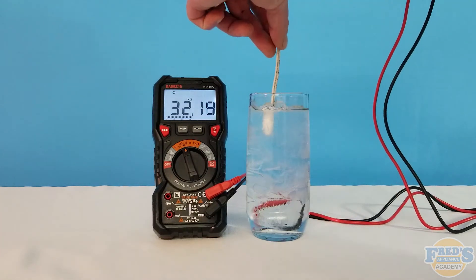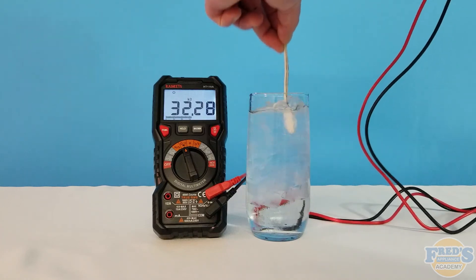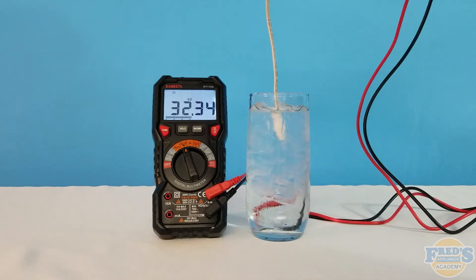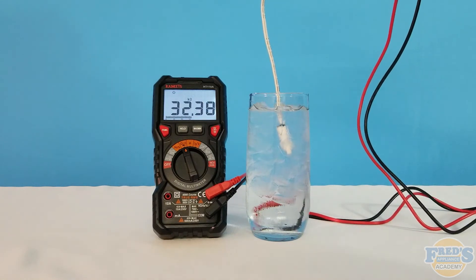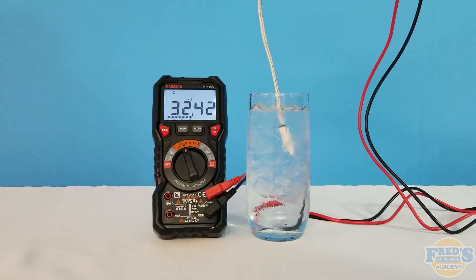So here we have a working and accurate thermistor. It read correctly at 73 degrees as well as 32 degrees. Now keep in mind these resistance values should be within plus or minus 10 percent.